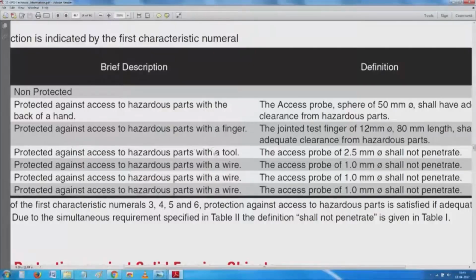So, going back again, when we made the IP20 cover, it has openings which are typically a little less than 2.5 millimeters. So, it is protected against access to hazardous parts with a tool. Access probe of 2.5 millimeters shall not penetrate. So, the advantage being that by mistake it does not go inside.